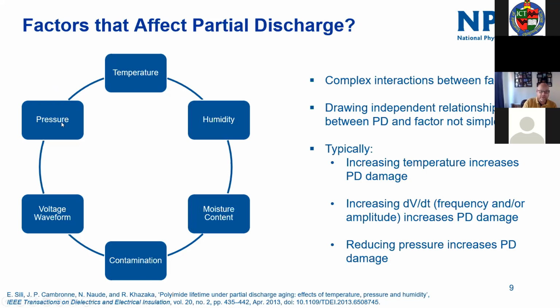Pressure I've already talked about, and that could be an important aspect. We don't really understand the effects of temperature very well, particularly in the range of dielectrics we're likely to be dealing with. Humidity is another factor - honestly, we don't understand which way it will affect things. Organic materials take up moisture depending on humidity and change their moisture content, but how that affects PD performance is largely unknown. Then there's the issue of contamination, which may affect surface insulation resistance by inducing electrochemical corrosion, which may in turn change the PD response as well.